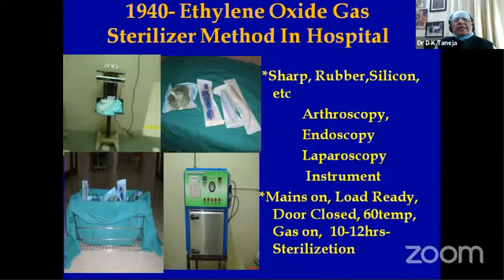Very important. Then coming to the different types of chemicals which are coming, ethylene oxide is now being very extensively used, and you can see that this is a small machine, ethylene oxide, and this ethylene oxide is very highly inflammable. So this is mixed with other gases, so the inflammability is reduced. So all sharp instruments, rubber, silicone, etc., your arthroscopy, endoscopy, laparoscopy instruments, all these things can be very well sterilized in your ethylene oxide machine.